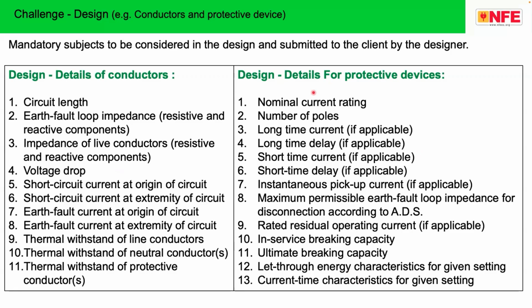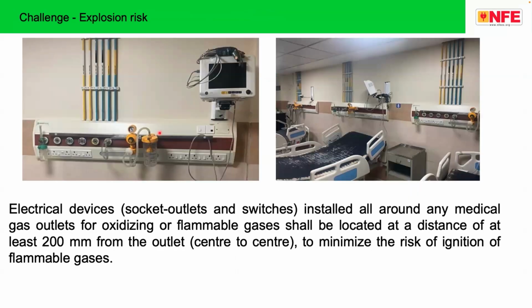Normally, protective devices are selected based on the load and short circuit current. The other parameters are mostly ignored. That's why I put this as a challenge. We are not in the 1970s, we are in 2025. Please ensure that the designer is making a design in a hospital considering all these parameters. Otherwise, your installation will not be efficient. It will not be reliable.